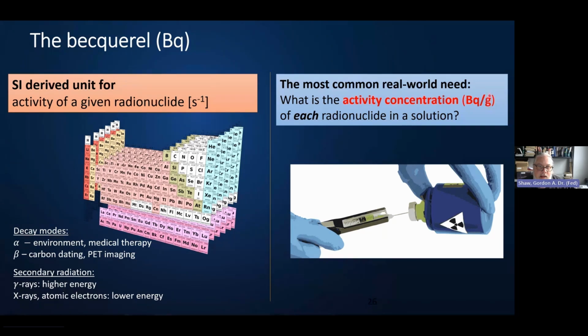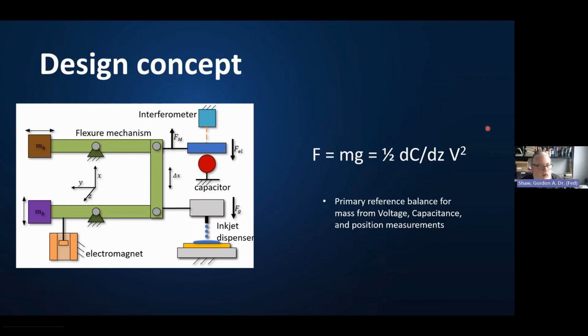And my job in the project is to be able to measure the mass of the liquid for these radionuclide activity measurements. And the design concept of this is to create a balance. And this all here is our balance mechanism and our capacitor that we use to generate the electrostatic reference force. And to this balance, we attach essentially an inkjet printer head. So we can dispense liquid from this inkjet printer onto a radioactivity sensor. And by measuring the change in mass as we dispense the liquid, we'll know exactly how much of the liquid is dispensed. So this will be a primary reference balance, once again, to determine the mass of the liquid sample from voltage, capacitance, and position measurements.